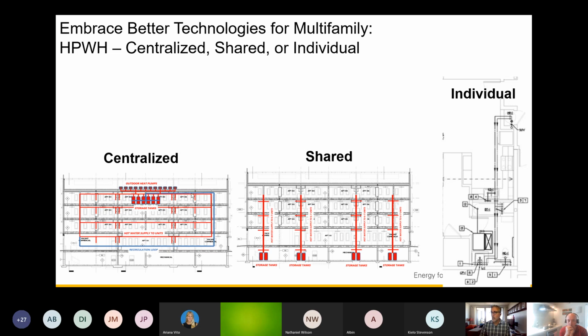So we've gone to a couple of other configurations that have benefits. One is the shared configuration, where we put two heat pump hot water heaters in an alignment through a chase to serve 6 to 8 units going up through that chase. The benefit is: when a centralized unit goes down, the whole building goes down. When this chase goes down, only 6 to 8 units in the building go down, not the whole building.